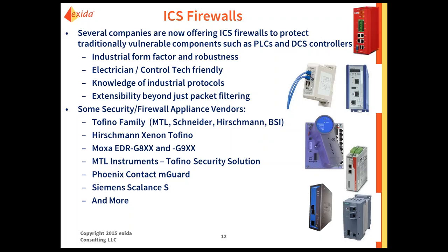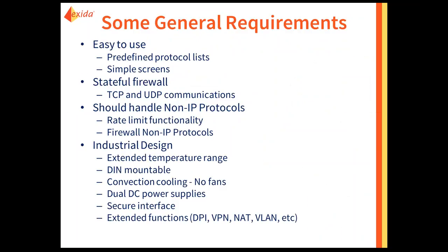Pick the vendor you are familiar with and working with. A number of vendors make firewalls for their specific networks — use those because implementation will be much easier since they're already designed for that architecture. General requirements to make life easier: predefined protocol lists for industrial protocols like Modbus, Ethernet IP, DNP3, FTE, and Delta V, so you can select them from a list instead of defining them yourself.